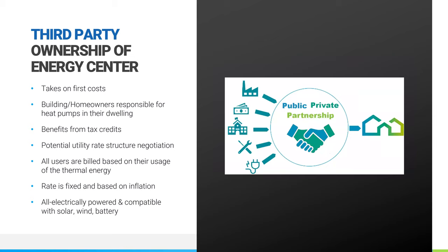One thing that has happened a lot on these community systems is it opens up third party ownership of the energy center, so all the underground piping, the wastewater heat recovery system, the geothermal bore field, all that stuff is owned by a third party entity. So what that does is it takes away the first costs from the low income community that might be coming into this, or whatever is connecting into this energy center loop field. The first costs of going this energy efficient route are not borne by them. So that energy developer then takes on those first costs. They get to benefit from the tax credits. Again, going back to that Fort Polk example, they then as an entity have the potential to negotiate with that local utility on different rate structures for that microgrid, if you will, community.